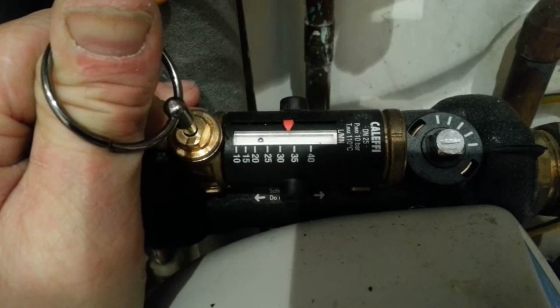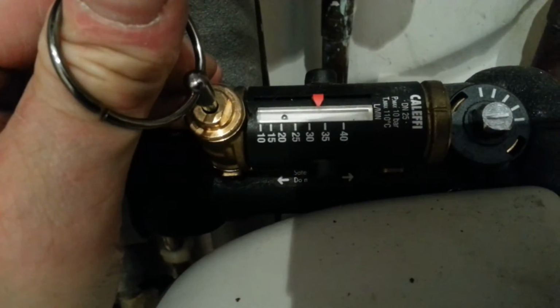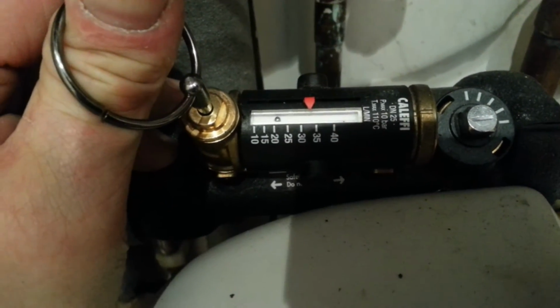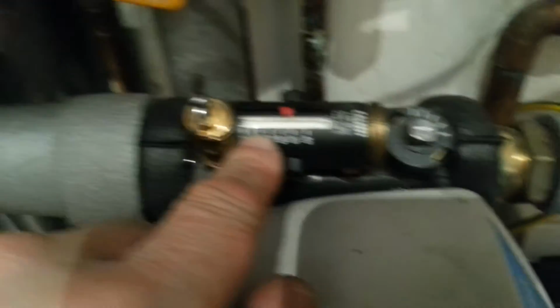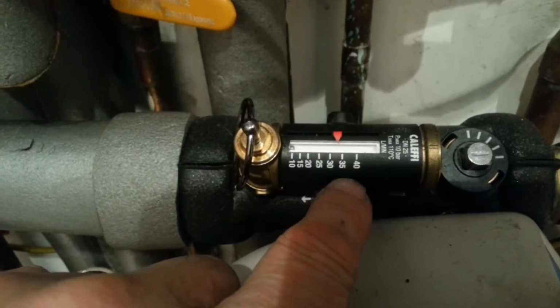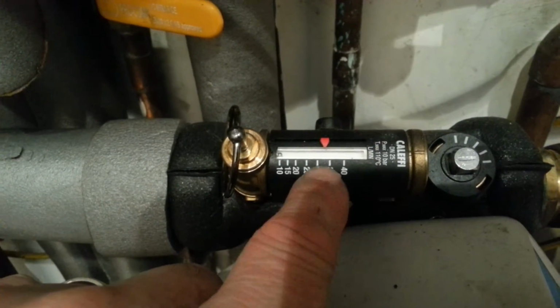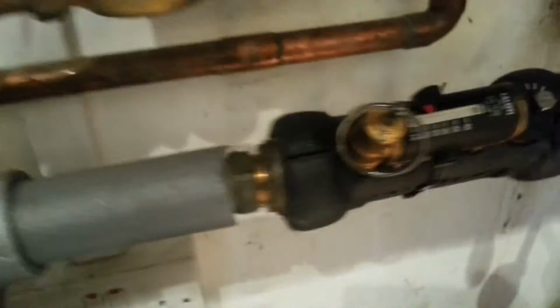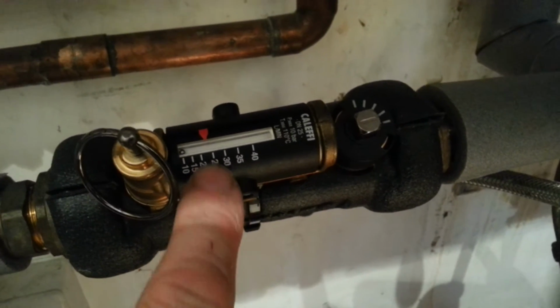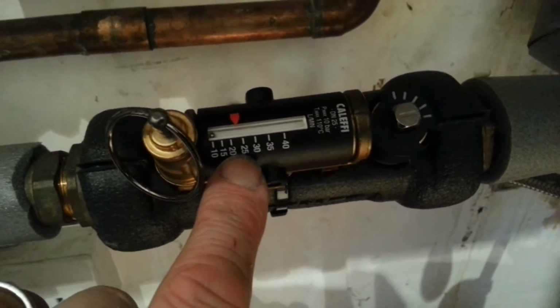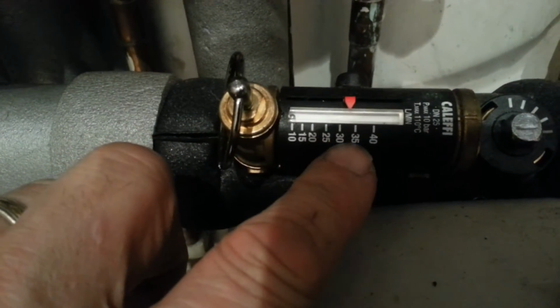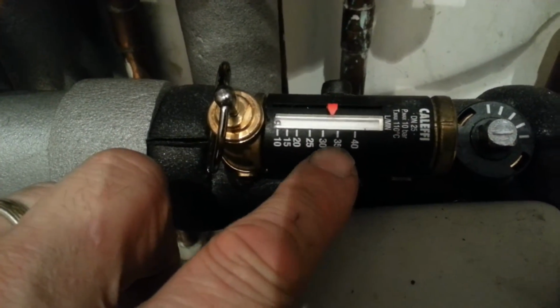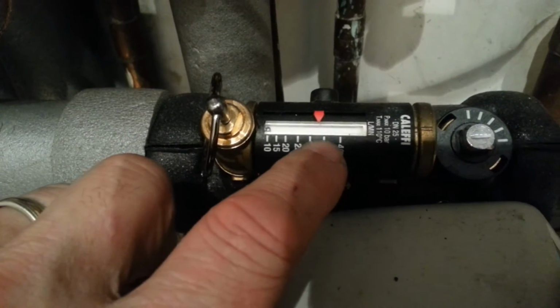Then if we turn on the heating circuit, it'll start to pull heat to the heating circuit. It might take a while, it's underfloor, so you won't see anything on this video. We'll see what happens. So as the flow changes on this side, this varies all the time. And the most important part is the flow on this side can be higher than the flow on this side. And of course we shouldn't exceed the maximum flow for this boiler, which is 24 litres a minute. But on this side we get flows of up to 34 litres a minute. And in fact with the alterations I've done today, possibly a little bit more.